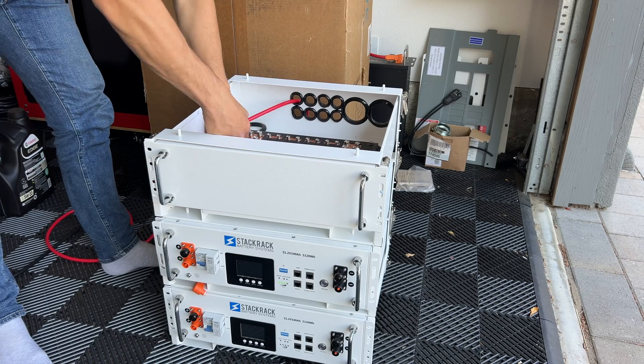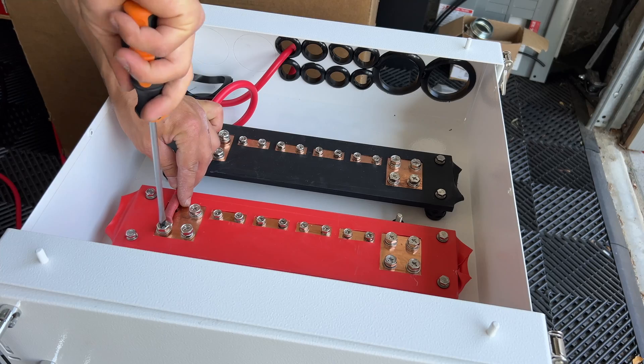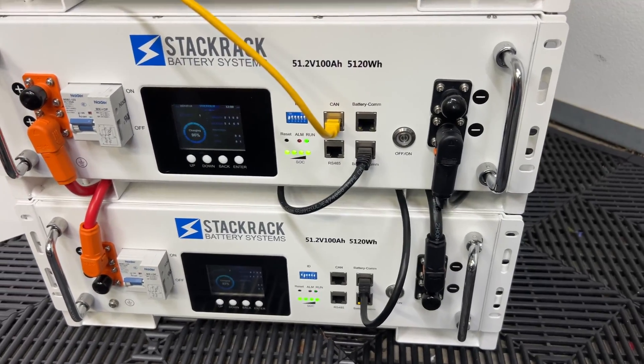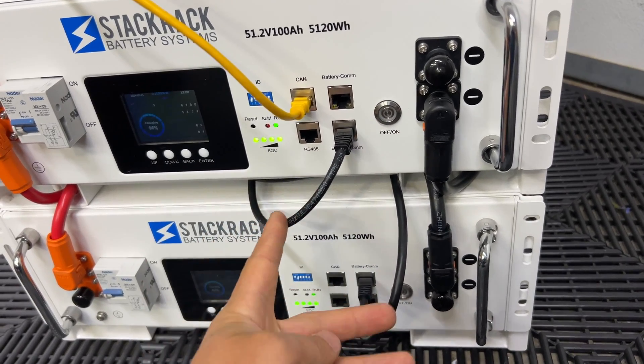On the back side of the combiner cabinet we have plenty of knockouts to run all wires and combine them on the bus bars. Here's all the battery wires connected together — now we can connect the inverter and run tests. For battery communication we're using the battery comm port, connecting two batteries together.